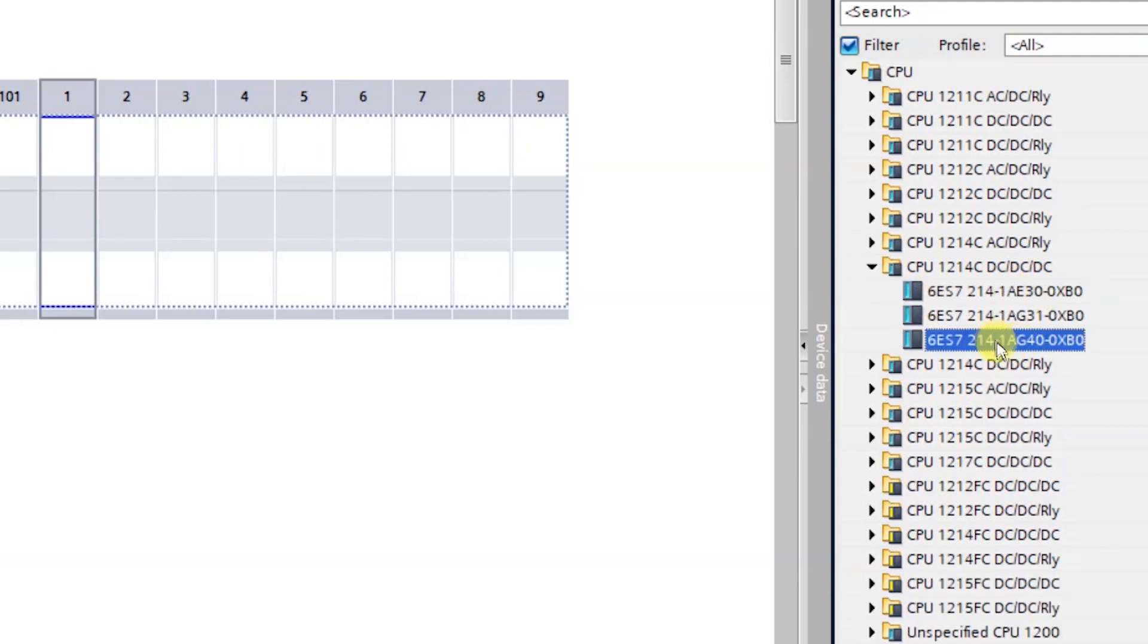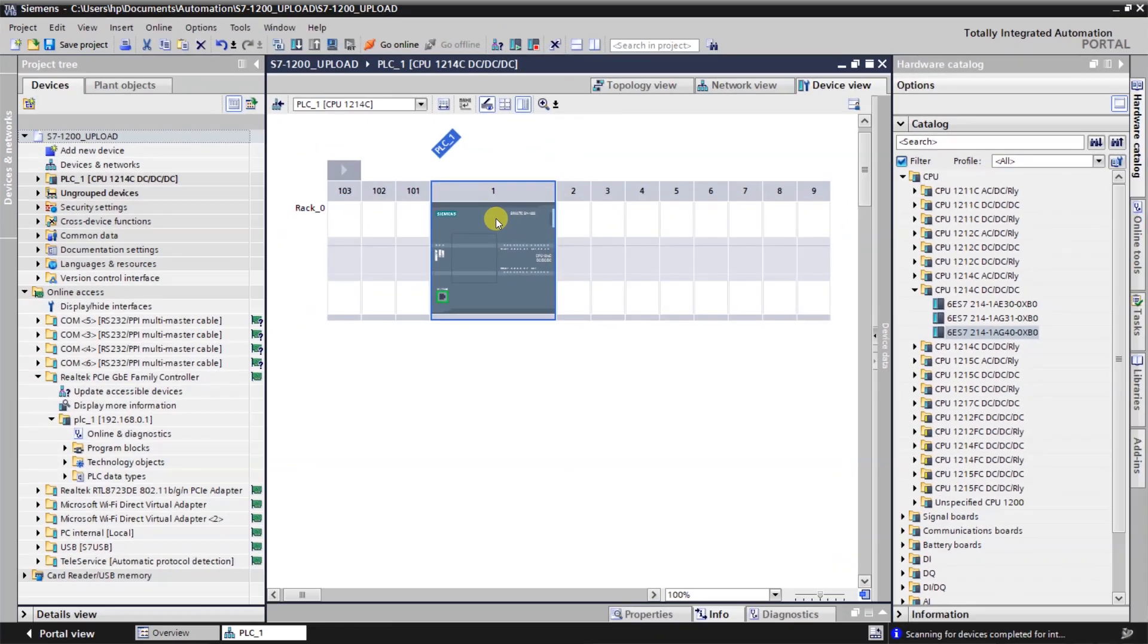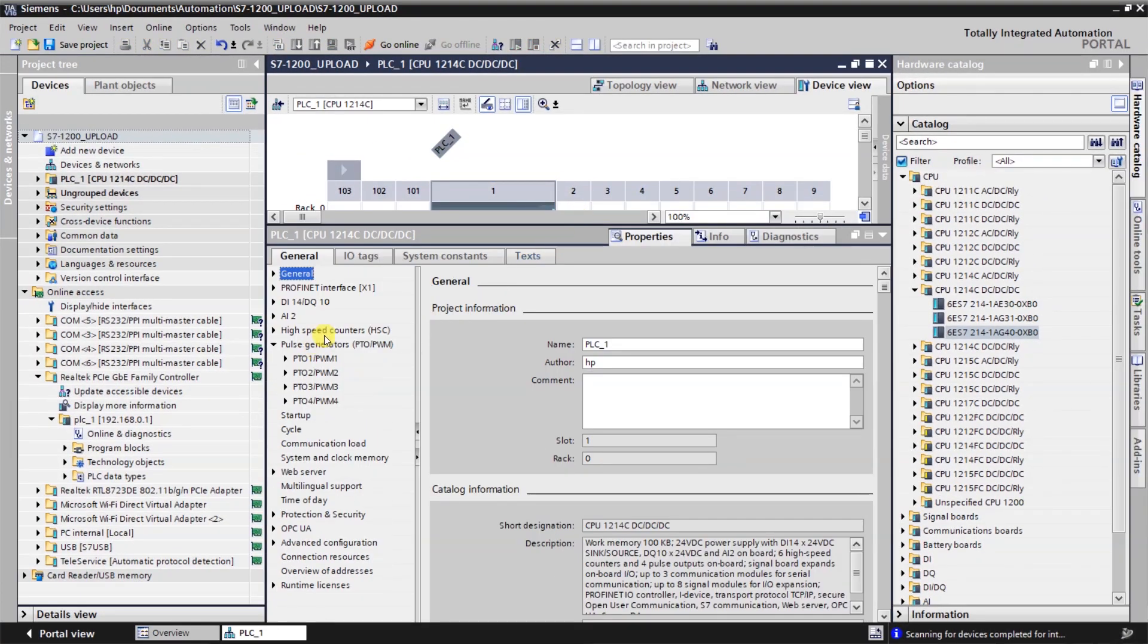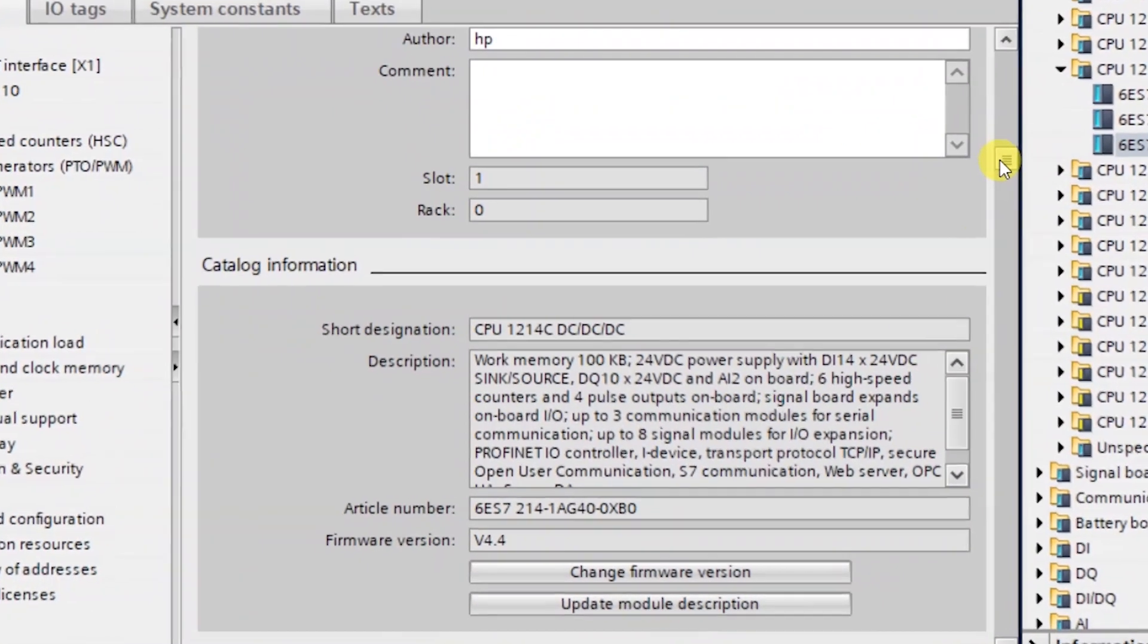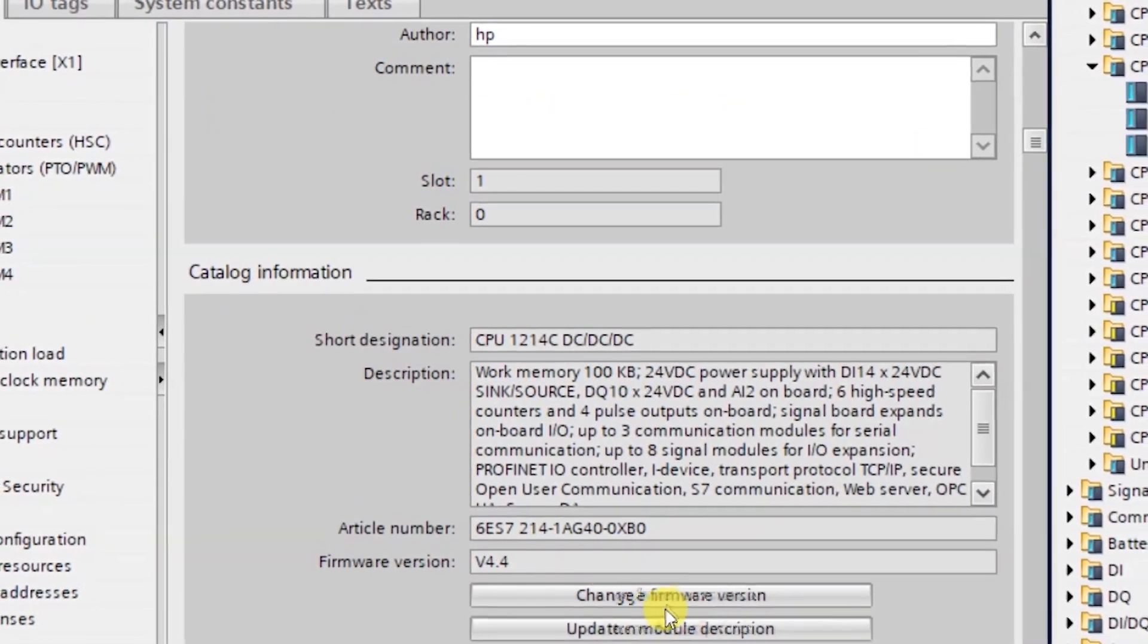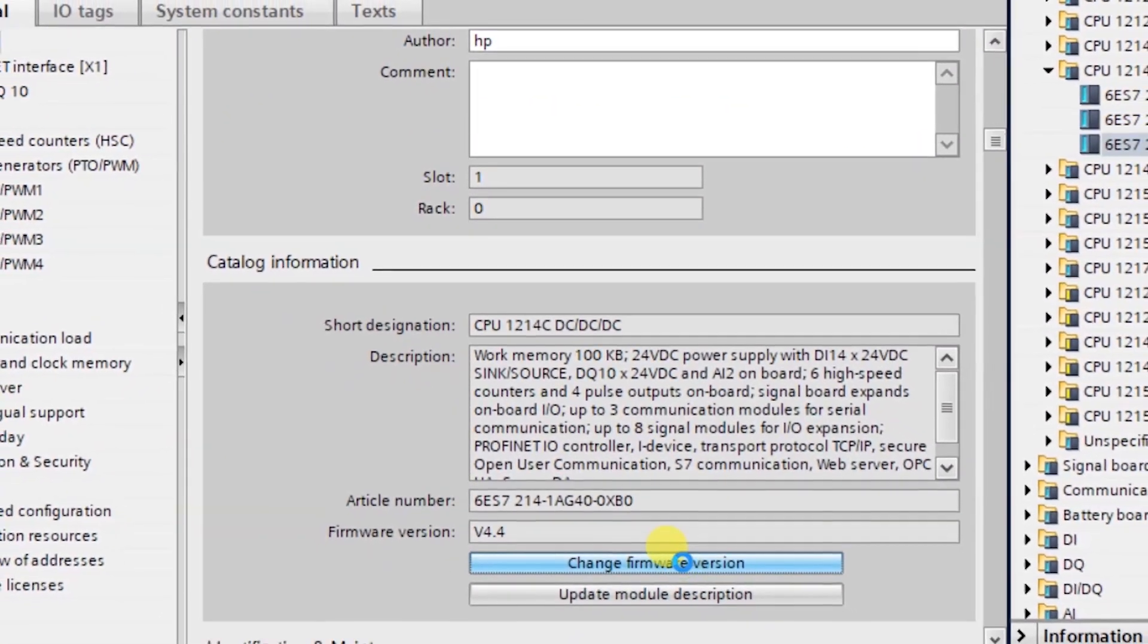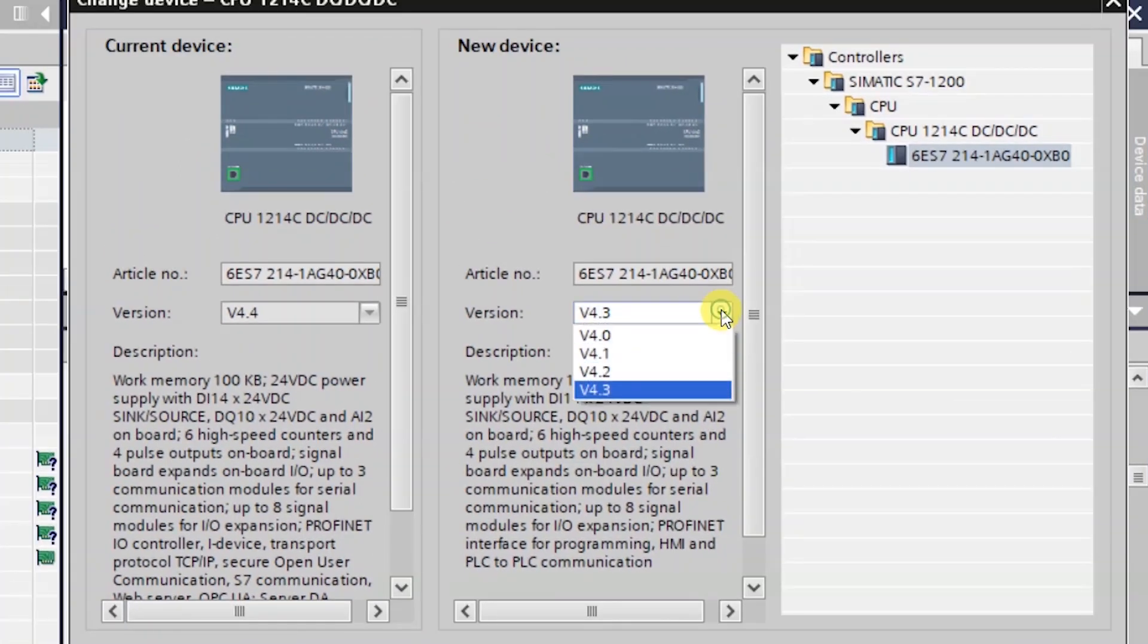Just drag and drop it in the first slot. Double-click on the PLC and go to the properties. In the general tab you can scroll down and you can change the firmware version. Click on this option and select the firmware version 4.2.